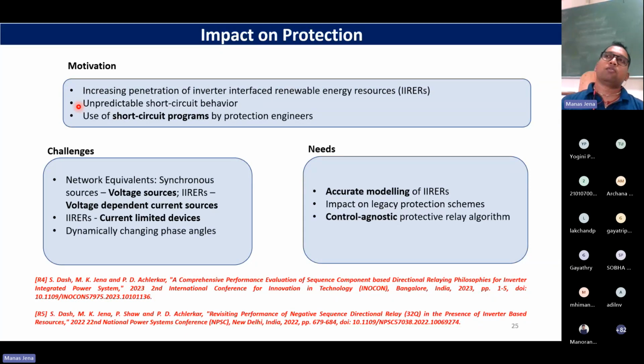So unpredictable short circuit behavior is not only an issue with the amount of fault current you can get from the inverter. At the same time, there is the control of the negative sequence currents during unbalanced scenarios, and how the negative sequence response will be from the inverters. Typically, protection engineers use short circuit programs and assume that the system is conventional and the sources can be assumed as voltage sources. But as far as IBRs are concerned, traditionally, it is a voltage dependent current source.